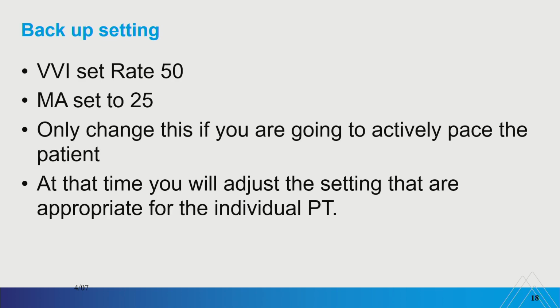Okay. The backup that we use at Mount Sinai Morningside does not have to be the backup that you use. You can use DDD as a backup, but it's much harder to get it to work right. If you're setting a pacemaker up on DDD mode and you want it to just be a backup, you are more likely than not going to have to shorten your PVARP and prolong your AV interval out to 300. Or else you're going to just continue to start V-pacing because every time it senses the atrium, it's going to trigger that secondary clock. It's only going to wait 170 milliseconds. What if I'm in a slight first-degree heart block, which is very common post-operatively? It's going to continue to just start V-pacing.